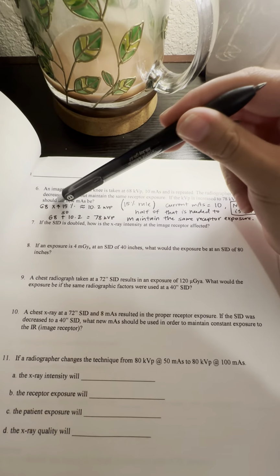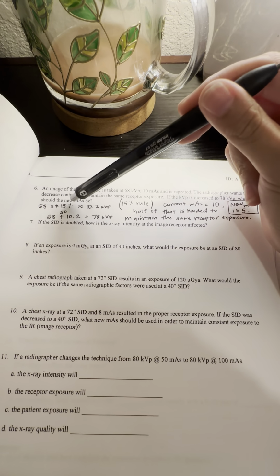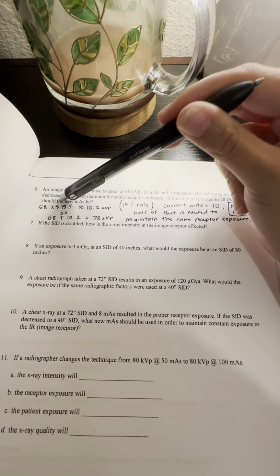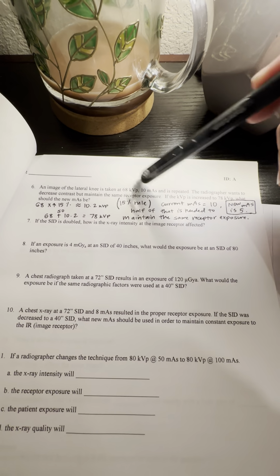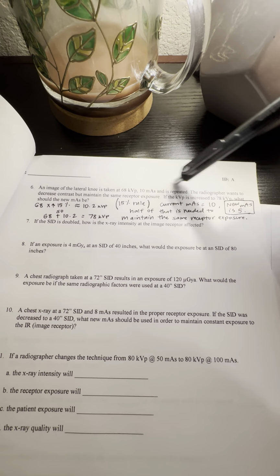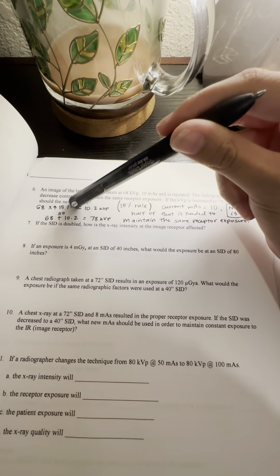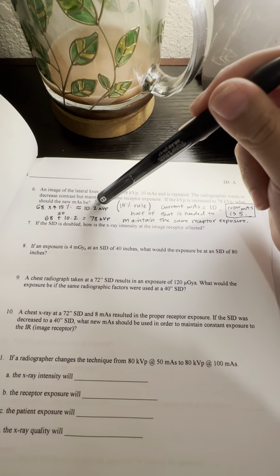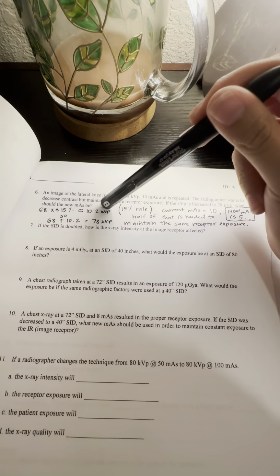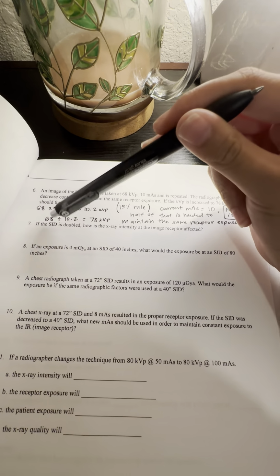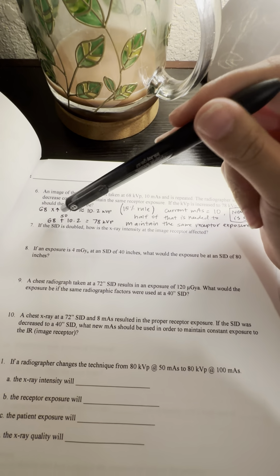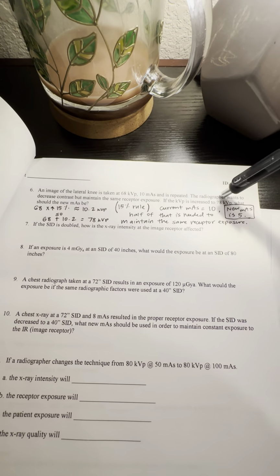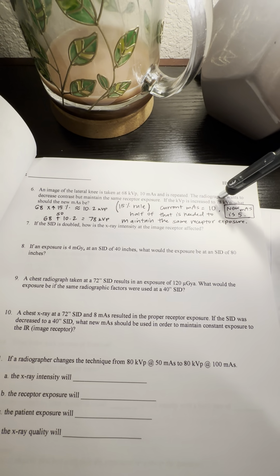So 68 was the first kVp. If we increase that by 15%, I multiplied 68 by 15% to see what the value is. Because essentially you would think that 68 to 78 is like a 10% increase. But actually the calculation shows that 68 times 15% is 10, so it's going to increase about 10 kVp, exactly 10.2. And 68 plus 10.2 shows that it equals 78, which is the new kVp, so that makes sense. That adds up.